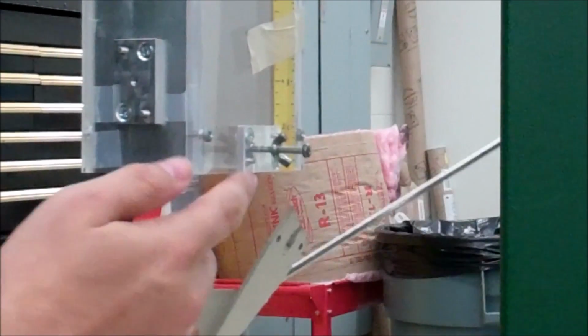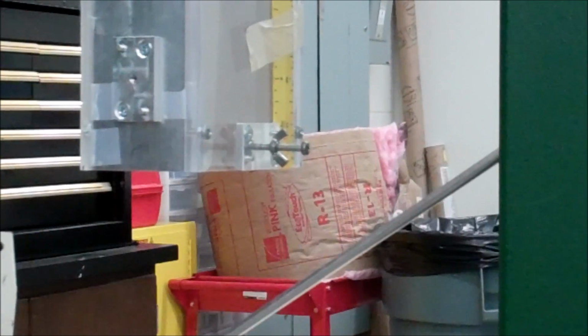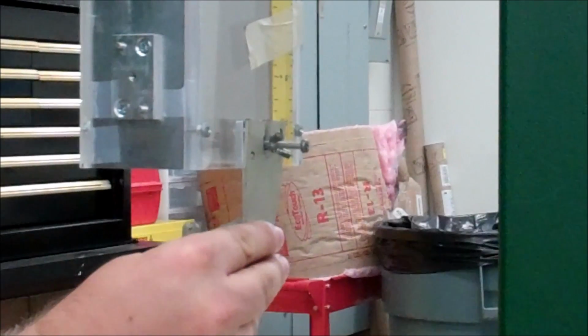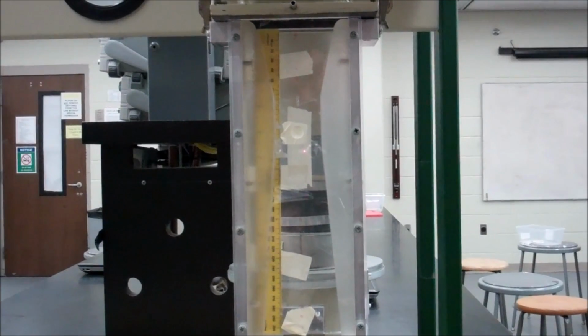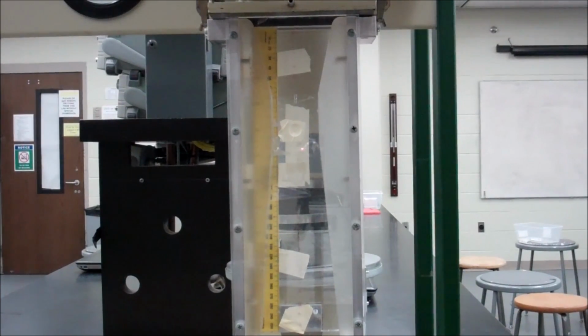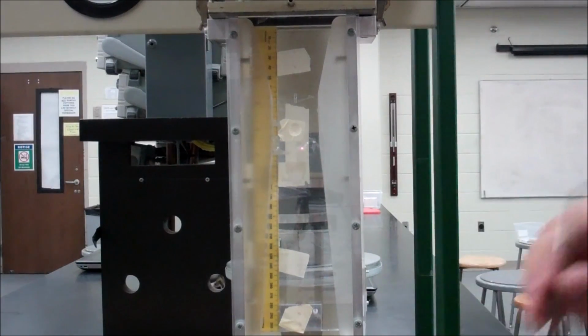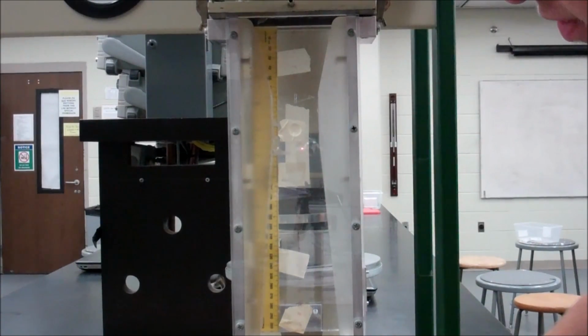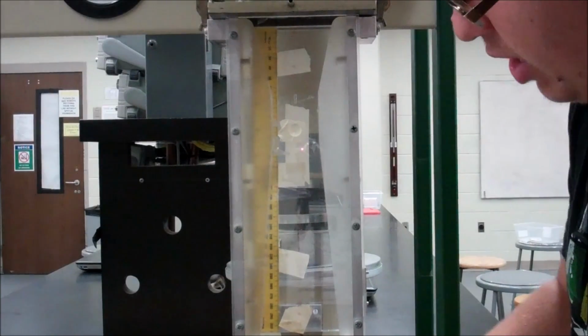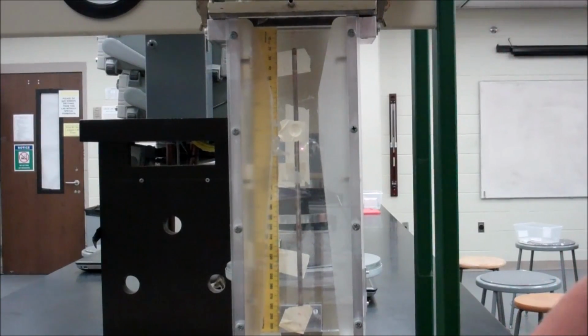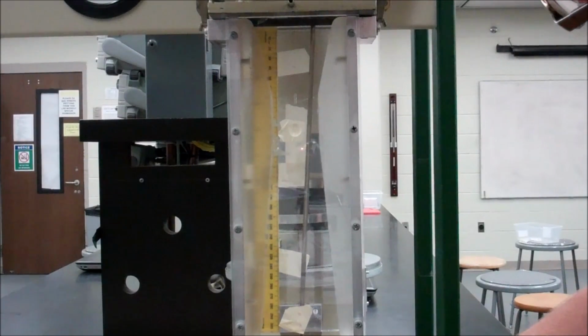So again, how you put this on is you have two little knobs here, you have two little holes here, you line it up, put it in, and screw it down tight. So you can see your channel here. The way to use a pitot tube is, the flow direction is going down towards the ground, so you have to put the pitot tube with the brass end pointing up, and you put it in from the bottom through here. And you can see it right here.